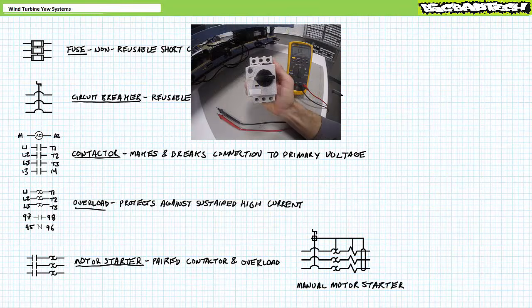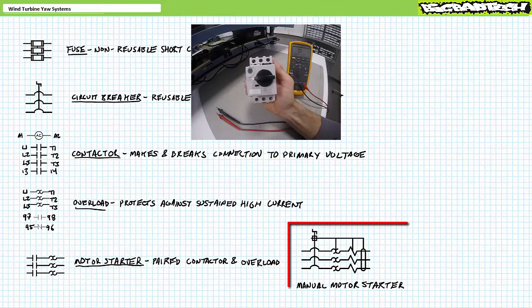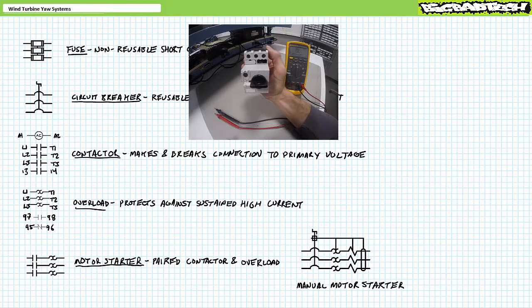A commonly available motor control element, known as a manual motor starter, combines the function of a circuit breaker, contactor, overload, and manual shutoff. You know the schematic symbol for a manual motor starter includes contacts that can be opened manually, as well as in the event of a short circuit or overload. Some manual motor starters, not all, may include an accessory means of locking them in a particular position as part of safe work practices should it be necessary to de-energize a particular branch of a circuit.